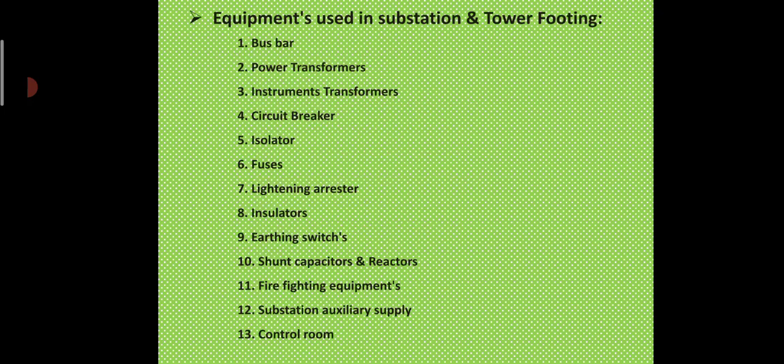Arresters should be located immediately adjacent to the transformers if the connections between the transformers and the bus are made by overhead lines. If a high voltage cable is used for connections, the arrester should be placed both near the switchyard terminals of the cable and adjacent to the transformer terminals.